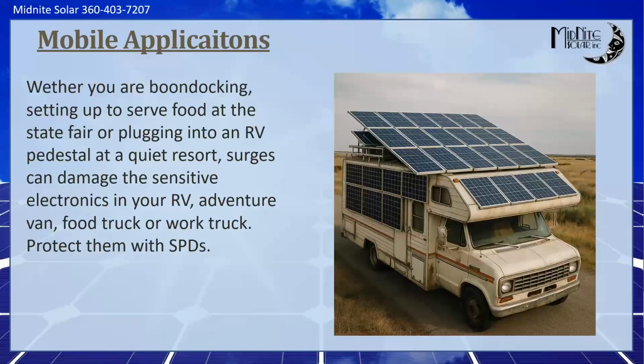But in this RV, for example, you've got 12 volts and you've got 12 volt appliances, and you probably have 120 volts off of that much solar and an inverter. So if that RV came in contact with 5,000 volts, if everything in the RV went to 5,000 volts, then it'd be 0 volts across anything for potential. And that's what your SPD is trying to do in a mobile application. If you take a bad surge, we're trying to keep everything the same, so your L1, your neutral, your ground are all at the same potential. Now those all three could be 2,000 or 3,000 volts compared to the pedestal you're plugged into during a strike. But as long as all three are at that potential, there's no delta between them, no voltage difference between them. There'd be no arcing over, there'd be no damage, and you would save your product.